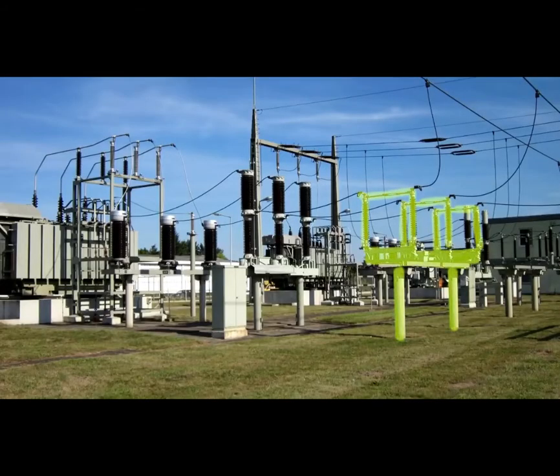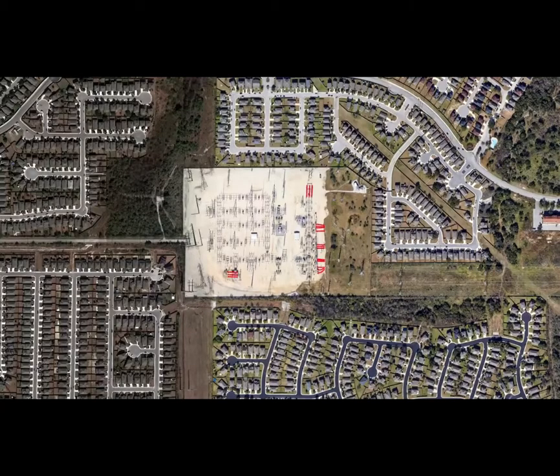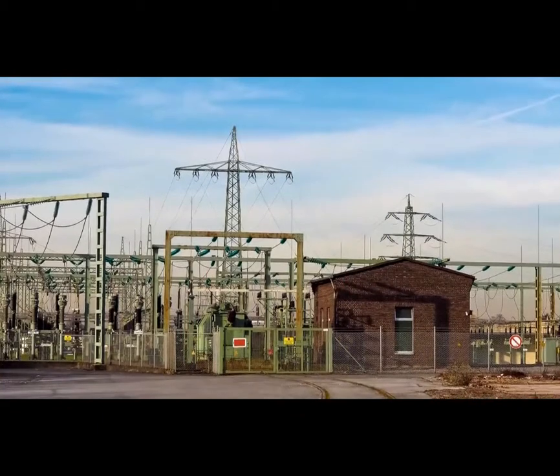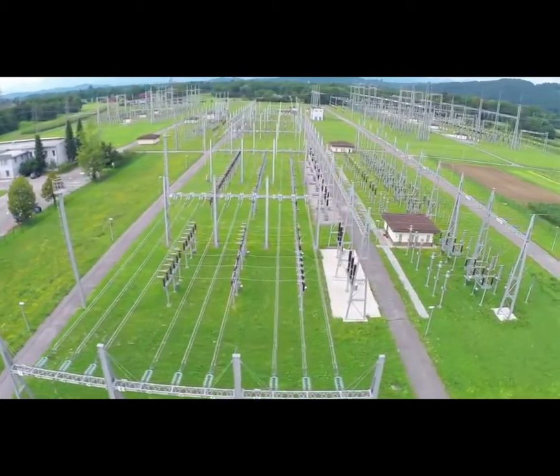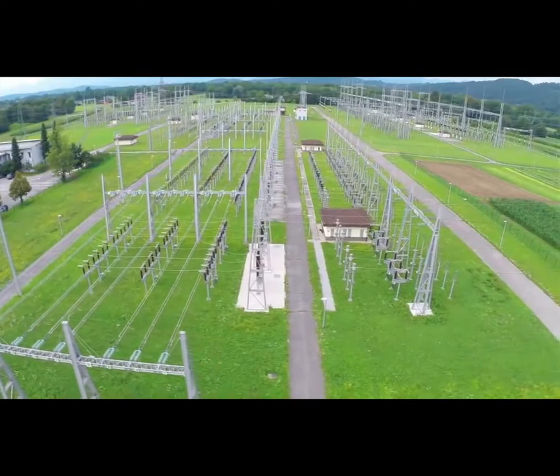The first and often simplest of these roles is switching. The general layout of a substation consists of some number of electric lines — called conductors if you want to fit in with the electrical engineers — coming into the facility. These high voltage conductors connect to a series of equipment before heading out to their next step in the power grid. As a junction point in the grid, a substation often serves as the termination of many individual power lines, creating redundancy so the substation stays energized even if one transmission line goes down. The connections to various devices are called buses — often rigid overhead conductors running along the entire substation — and the arrangement of the bus is critical to overall reliability.